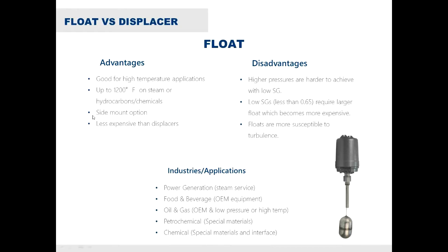The advantages for float-type technology over a displacer are going to be temperature. With a float, the only parts weakened by temperature are solid metal, so you can actually achieve very high temperatures — upwards of 1,200 degrees F — for steam applications. Another advantage is a side mount option, since you can't really get a side mount option for a displacer mechanical level switch. Float-based technologies are also typically less expensive than displacer-type technologies.